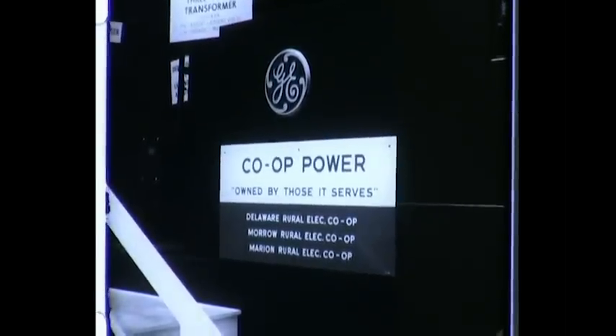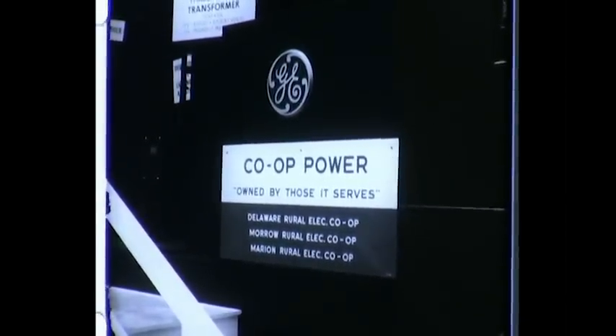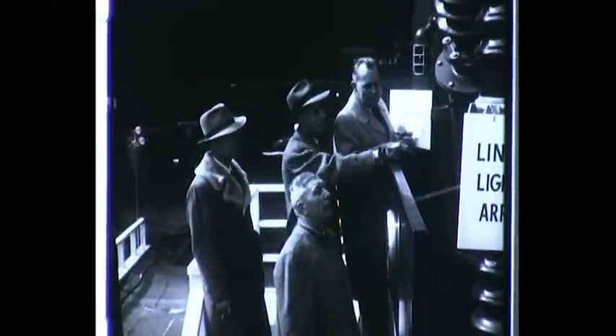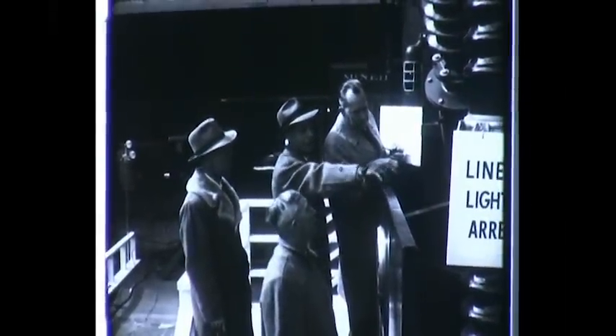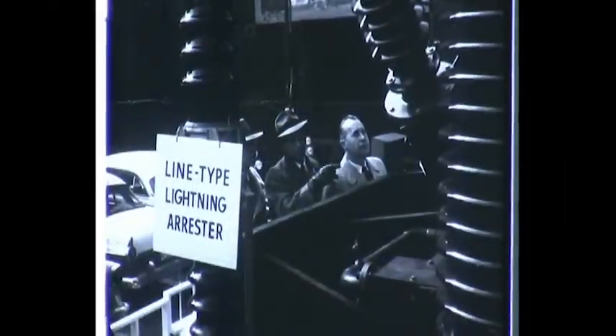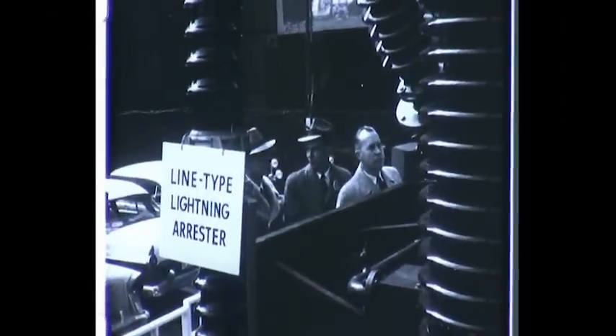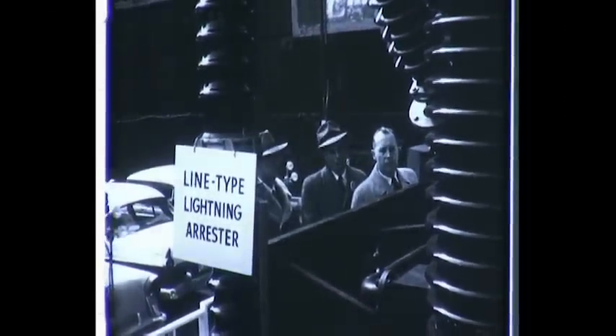An entire new market is now available to agency salesmen since there has been a recent relaxation of these restrictions. Now REAs may use 3-phase transformers in substations. 1 3-phase transformer costs far less than 4 single-phase units. In fact, it even costs less than 3 single-phase units. REAs can effect a considerable saving by using General Electric 3-phase RM transformers and relying on a mobile unit for the standby capacity.